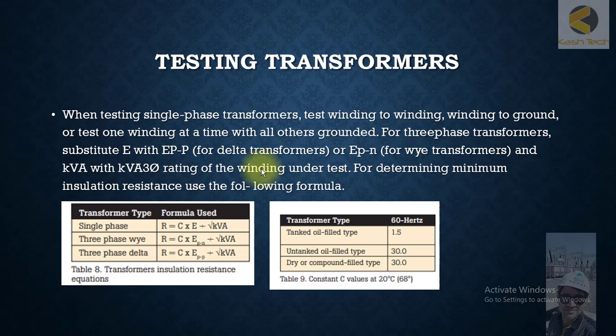Another method is to connect the positive lead to the HV or LV winding, ground the LV with the ground, and take the reading together. So these are all different methods to test the transformer.